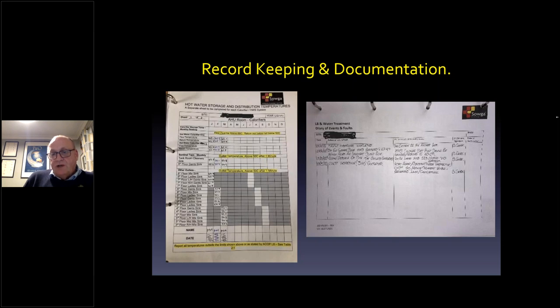What we've done with ours, because of the low occupancy in a lot of the buildings that we look after, is reduce the level of the tank water. We've even in some cases said, well, you don't need to have cold water storage tanks. There is no need to have them. And if you can agree on the risk that you don't need to have them, take your cold water storage tanks out. It just eliminates again one area where Legionella can breed.